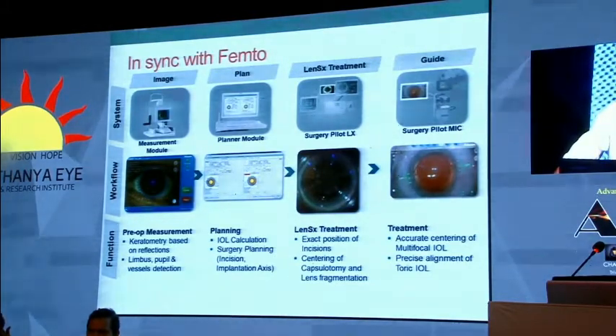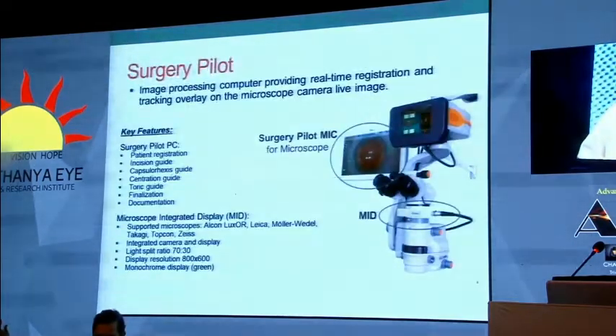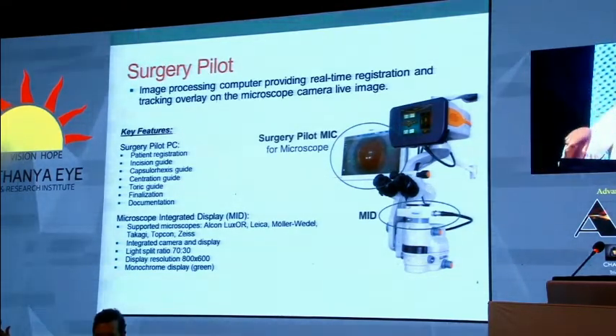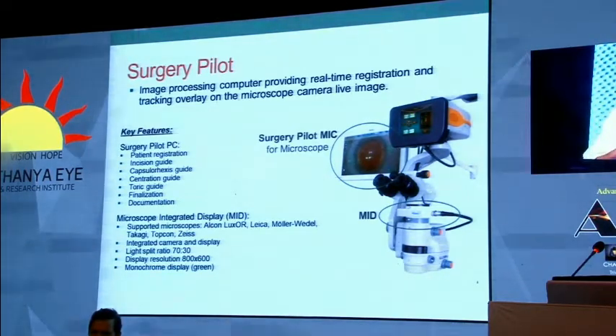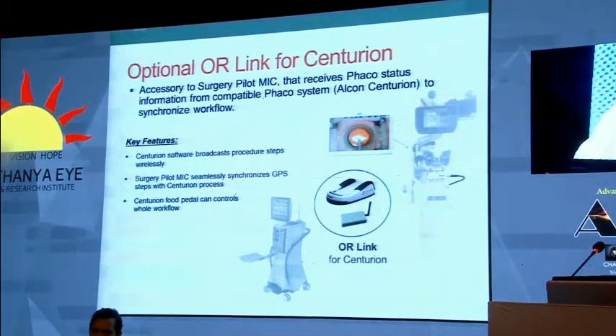Another important thing with the Verion is you can sync it with both your femto laser as well as the Centurion, so all calculations for the femto can be pre-planned using the Verion planner. The surgery pilot module handles patient registration, guides you to do the rhexis, lets you choose the rhexis size, and guides all incisions. Parameters displayed during surgery are optional and can be switched off if you find them disturbing. At the end of surgery you can use it for aligning your toric lens and to verify exact centration, especially for multifocal lenses. The Bluetooth foot pedal with the Centurion links it directly to the Verion, so with the movement of your foot switch you can align the lens.